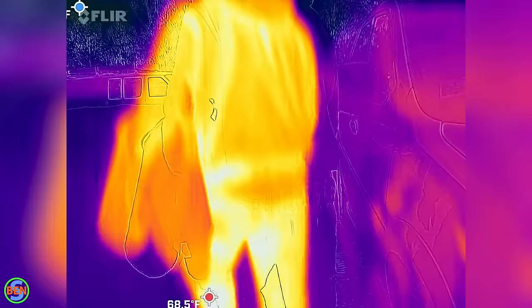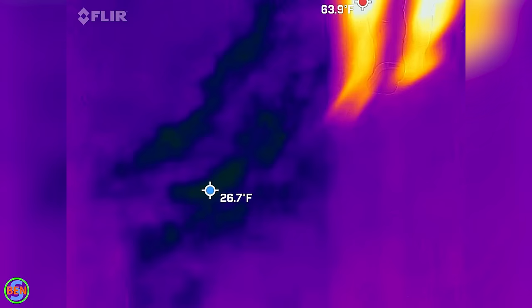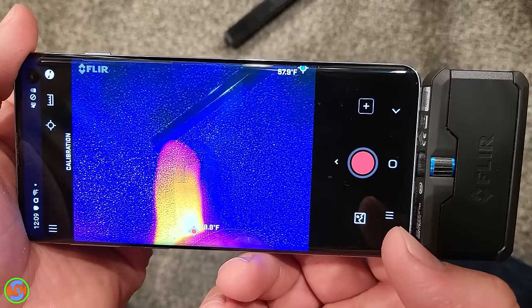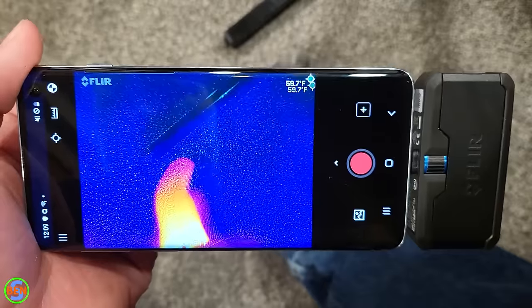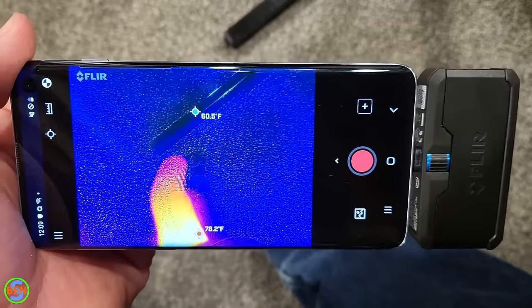Unfortunately the existing piping is just not sound enough to really last much longer, but this brazed repair was a great solution to get it up and running. You might have noticed that in some of the video the image wasn't quite lined up with the thermal image — that's just because I didn't have the camera alignment set quite right.